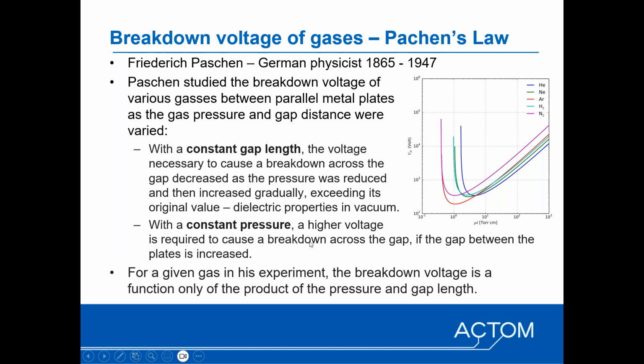The other conclusion that he made, at constant pressure, you require higher voltage to break down for larger gaps. And as I mentioned before, the bigger the spacing between your electrodes, the higher voltage you require to break down the gap.